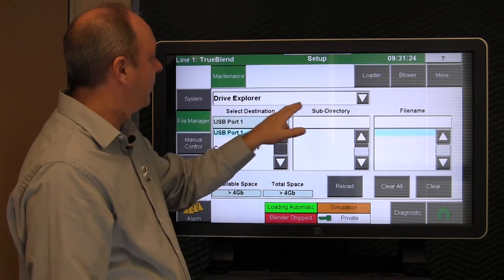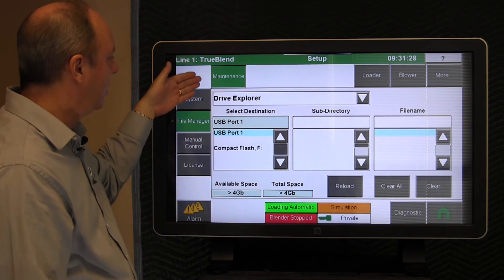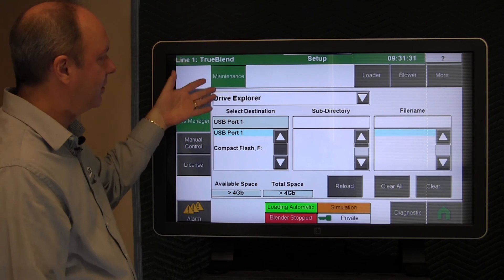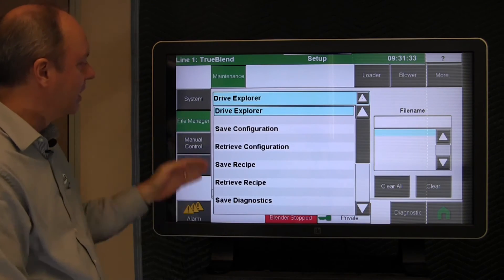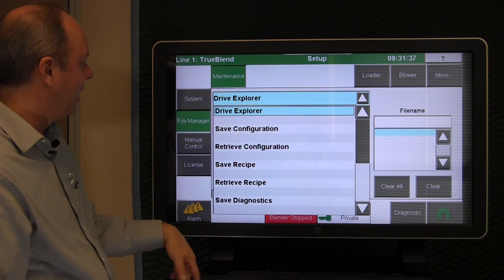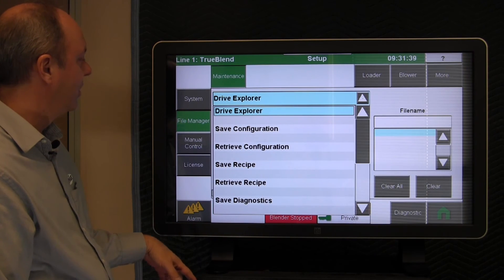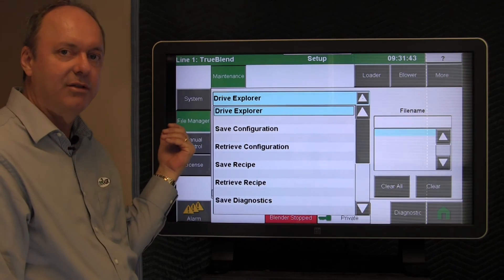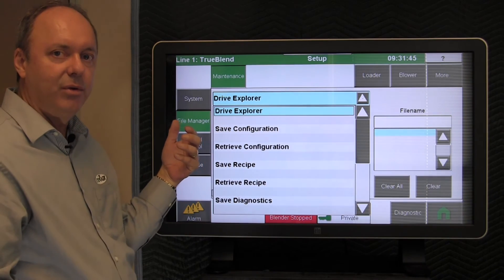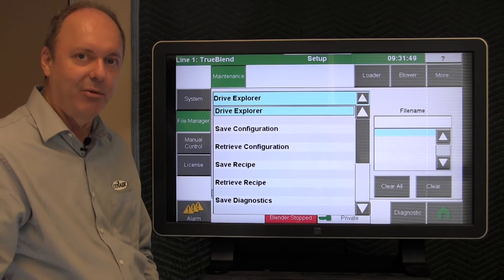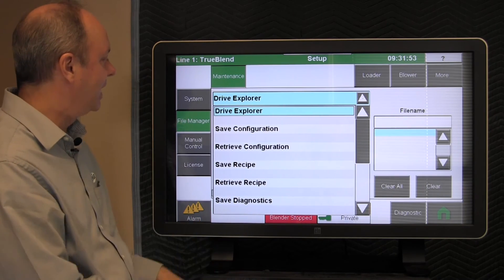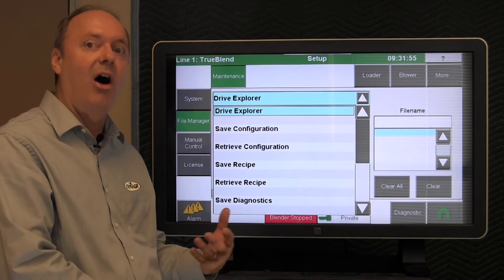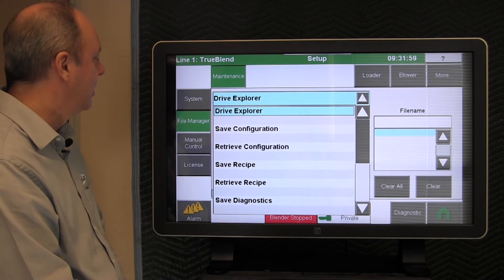And then the default is Drive Explorer, which is just the home page for the internal workings of the system itself. So you would tap this, and you get a list of different things that you can save off. And we're looking for diagnostics. You can also save the configuration off, and you can keep that stored in a desk if you'd like. If you suspect somebody changed a configuration parameter and you want to reload the configuration, then you would bring it back out on the USB stick and put it back in and retrieve the configuration back off.